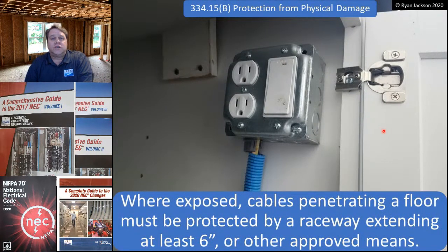334.15(B), protection from physical damage, where exposed. Make sure you read those first two words, because I've had inspectors that said you had to do this throughout the whole building. Now, where exposed, cables penetrating a floor must be protected by a raceway that extends at least 6 inches up through the floor or by other approved means.